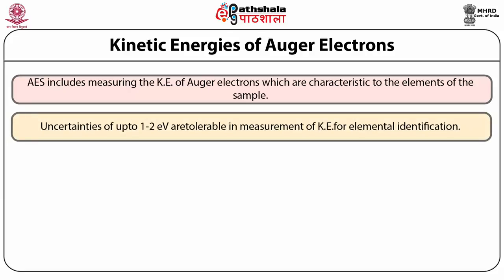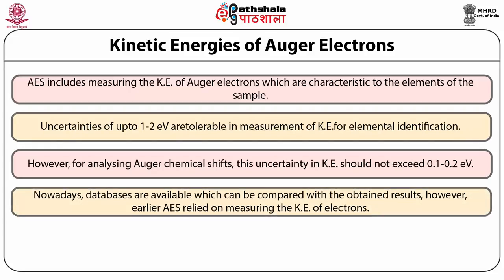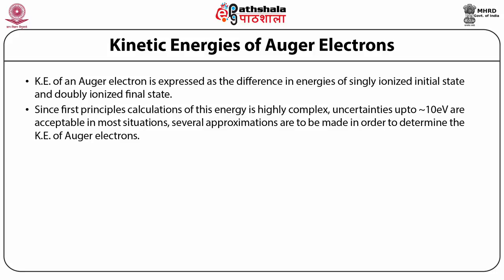Uncertainties of 1 to 2 electron volts are tolerable in measurement of kinetic energy for elemental identification. However, for analyzing the Auger chemical shift, this uncertainty should not exceed 0.1 to 0.2 electron volts. Nowadays, databases are available which can be compared with obtained results. Earlier, AES relied on measuring the kinetic energy of electrons. Approximations are made in order to determine the kinetic energy of Auger electrons.